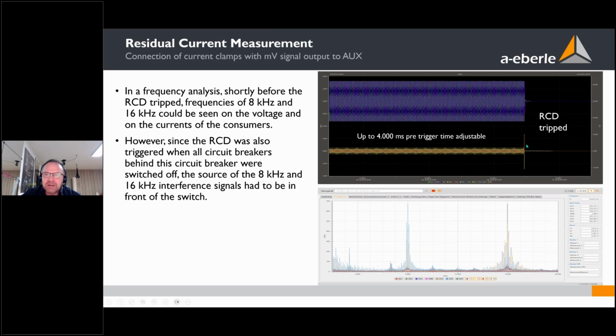The RCD tripped here, and with the software I'm analyzing on which current the RCD trips. In the FFT coming out of this oscilloscope picture, there's no big value at 50 Hertz. 50 Hertz would indicate an isolation problem. But in this constellation, on the current, we see only 8 kilohertz and 16 kilohertz. So this RCD will trip on supraharmonics, 16 kilohertz. So where does the 16 kilohertz come from, because we switched off all the devices in this office?